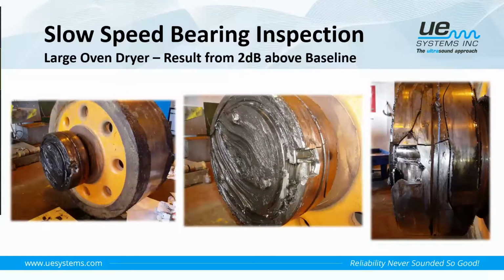After they took it out of situ, they sent me pictures of the damaged bearing. As you can see from the images, there were some severe cracks. Part of the outer race fell off, the cage inside had been damaged, and one of the rolling elements had moved 90 degrees. So this was a great find, a good way of identifying a problem at an early stage. It would have failed dramatically at some point, but we caught it early enough to get the work done in a scheduled way.